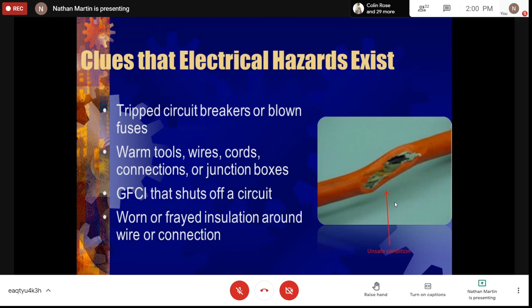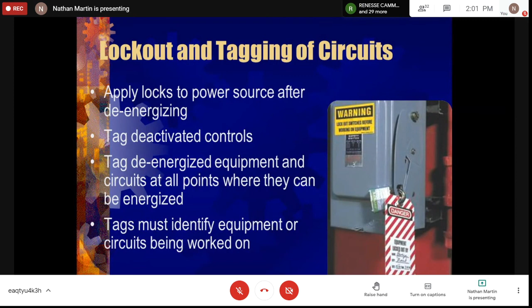We're talking about lockout and tag out. We mentioned it earlier, but here's how it's done in some cases - they use a small padlock and a tag. The tag must indicate that the circuit is locked out and being worked on. You need to apply locks to the power source after de-energizing, tag the deactivated controls, and tag the de-energized equipment and circuits at all points where they can be energized, since most of the time it can be energized at various points. Tags must identify the equipment or circuits being worked on. For instance, you might not be able to lock out the entire panel, but you can buy specialized lockout devices used to lock individual breakers in place.